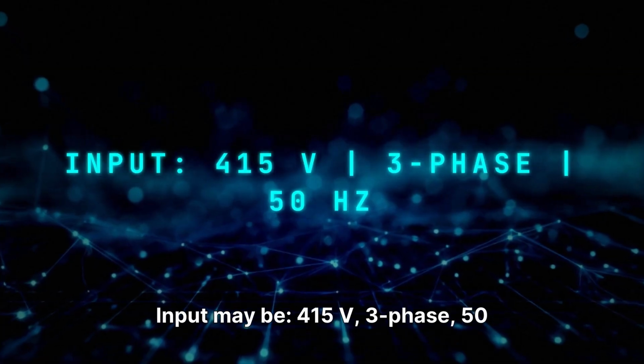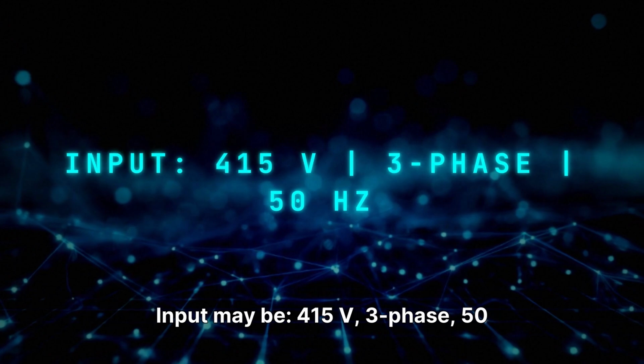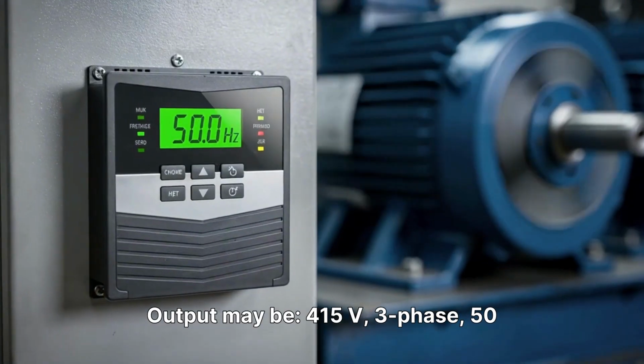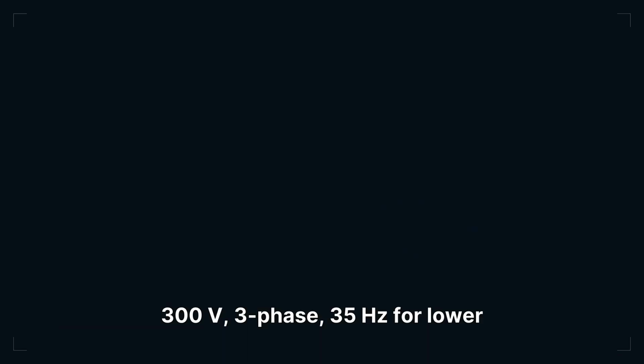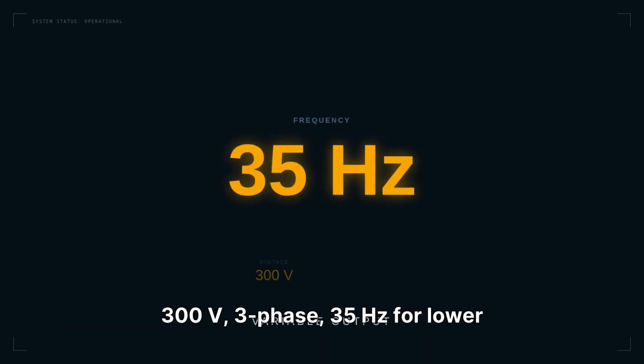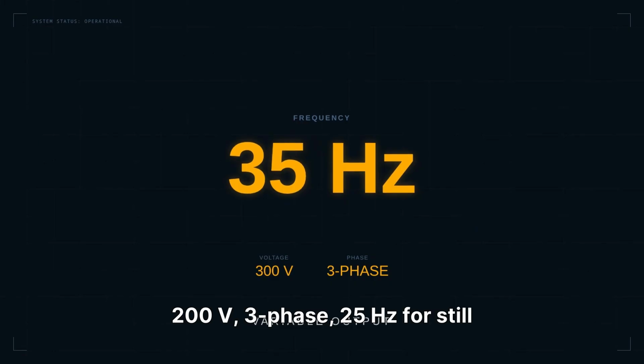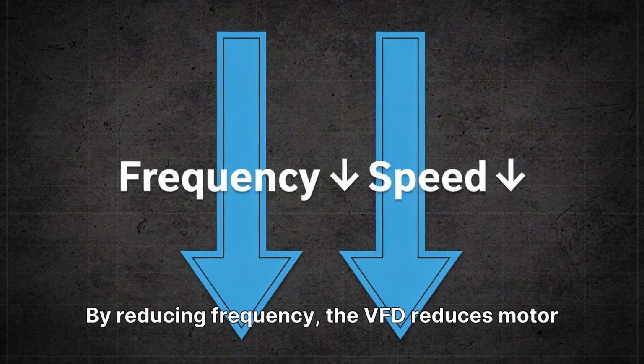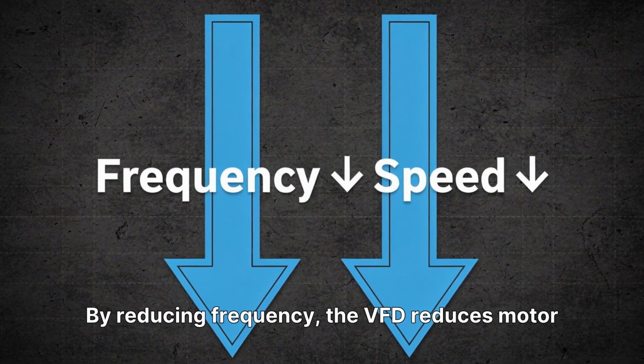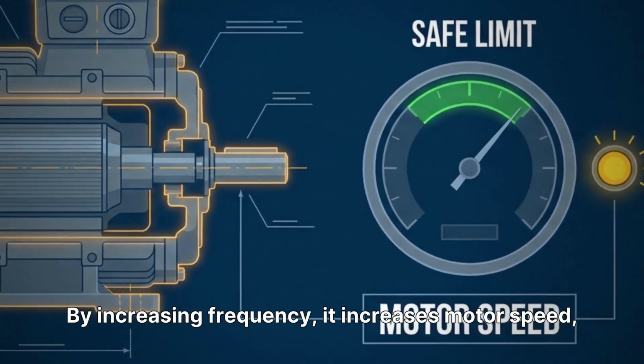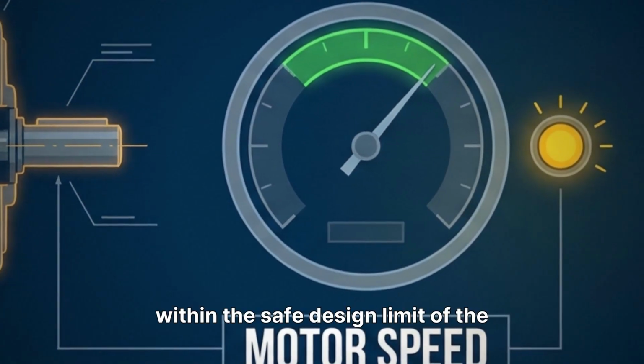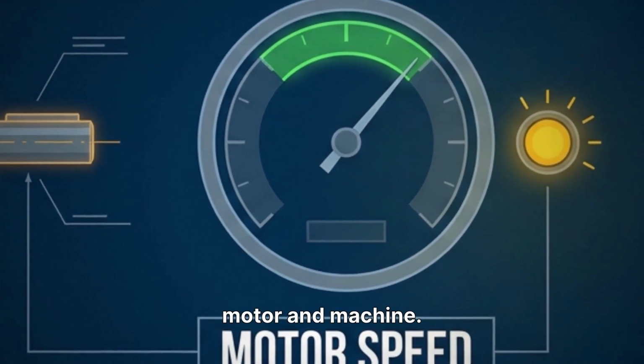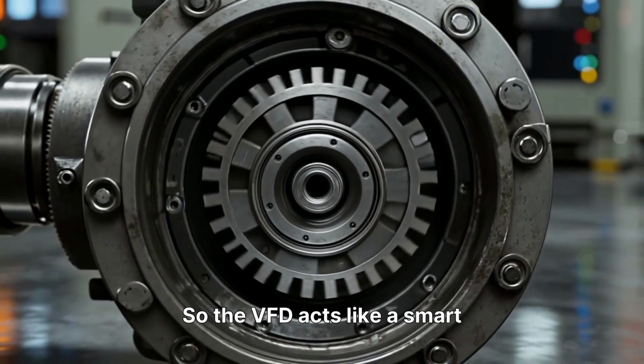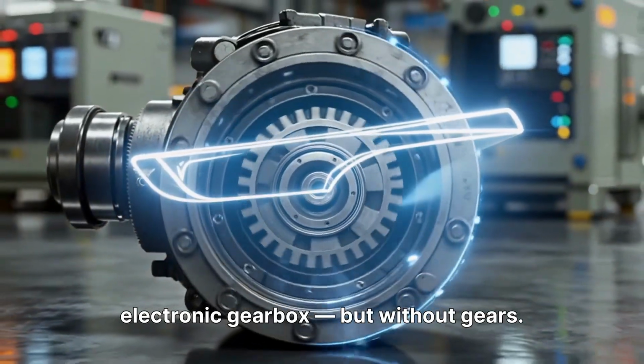Input may be 415 volts, 3-phase, 50 Hz. Output may be 415 volts, 3-phase, 50 Hz for full speed, 300 volts, 3-phase, 35 Hz for lower speed, 200 volts, 3-phase, 25 Hz for still lower speed. By reducing frequency, the VFD reduces motor speed. By increasing frequency, it increases motor speed, within the safe design limit of the motor and machine. So the VFD acts like a smart electronic gearbox, but without gears.